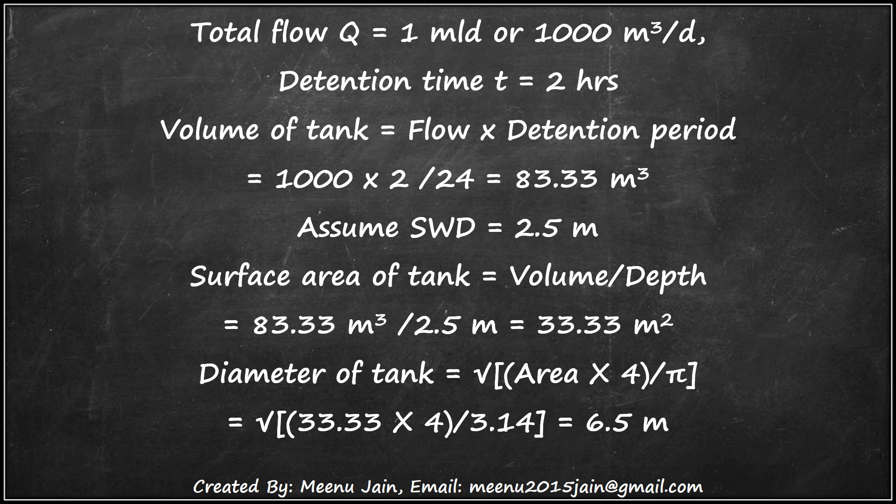Volume of tank equals flow multiplied by detention time, that is 1000 multiplied by 2 divided by 24, giving 83.33 cubic meters. Assuming side water depth is 2.5 meters, surface area of tank equals volume divided by depth, that is 83.33 divided by 2.5, giving 33.33 square meters.